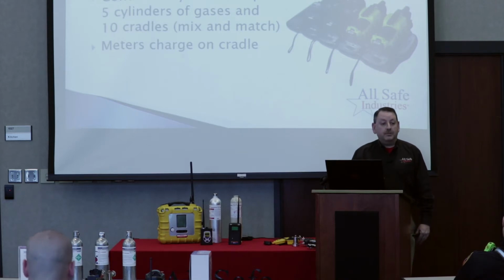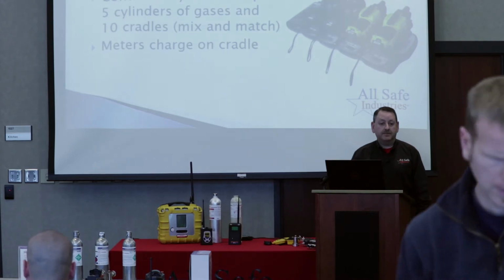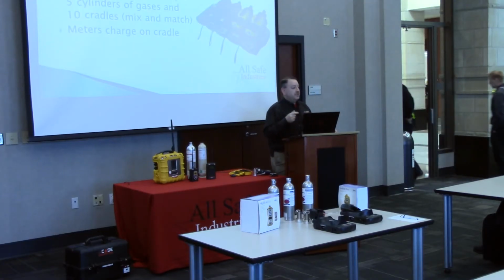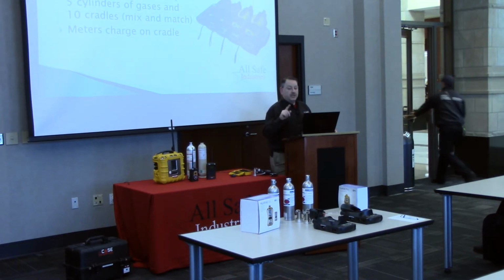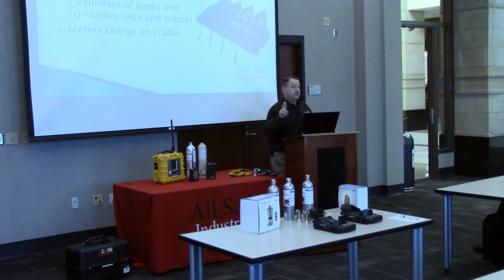There's also what we call the AutoRae 2 system. And the system puts an extra piece on the end called a controller, and then I can bank multiple cradles together. And I can bank up to 10 cradles, and I can mix and match them. I can have ToxRae Pro cradles, I can have 4-gas cradles, I can have multi-gas cradles, and I can mix and match up to 10 altogether. The other big difference between running a cradle only compared to running a full controller system is the cradle onlys can only accept 2 cylinders of gas.